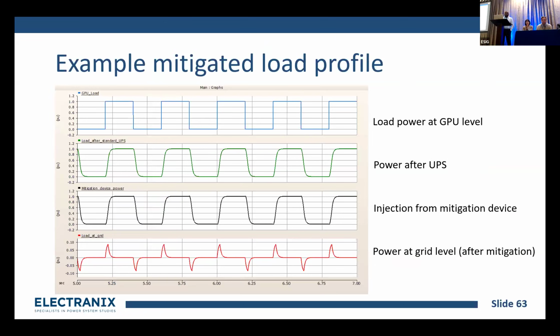So this is a typical waveform. This is not from a simulation. Even though this looks like PSCAD, I just mimicked it this way to protect the non-disclosure agreement. So this is not from a real simulation. If you look at the load profile, you can think of a step load profile, like a square wave. And then after the UPS, the power supply, you can see a little bit of a ramp or kind of a shape applied to those vertical lines. And the injection from the mitigation device is the third one, very similar to the first one, but there is a difference between those two. It's not visible in this one.